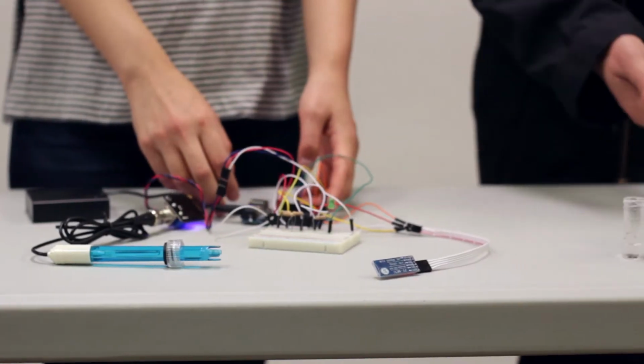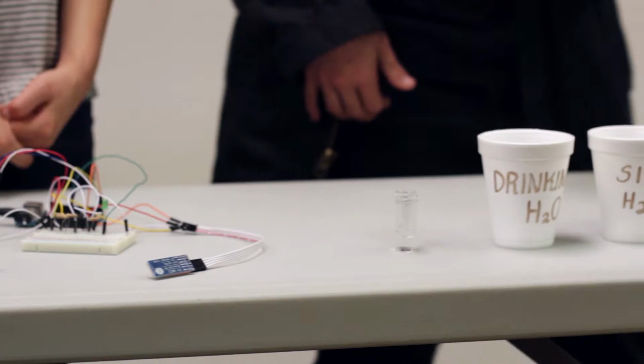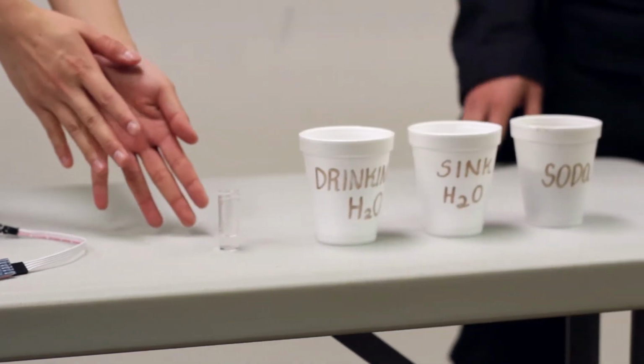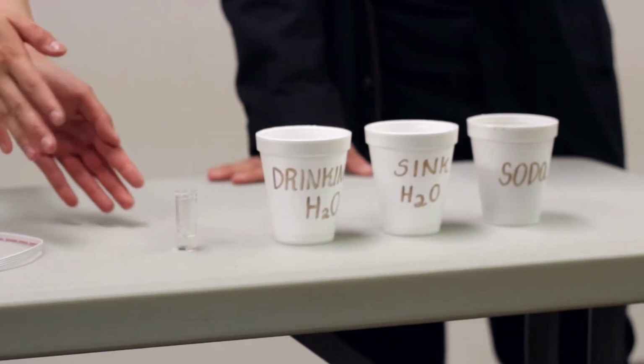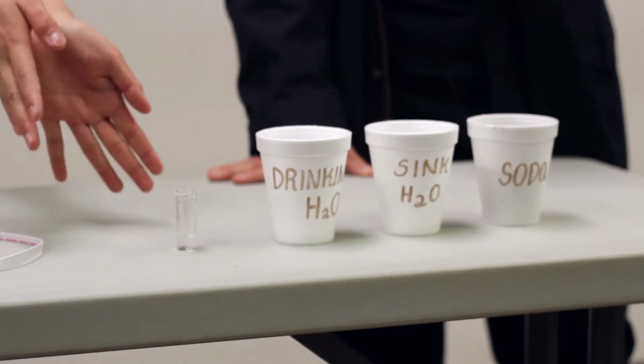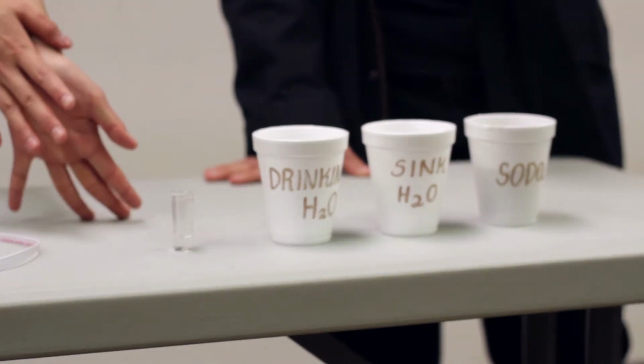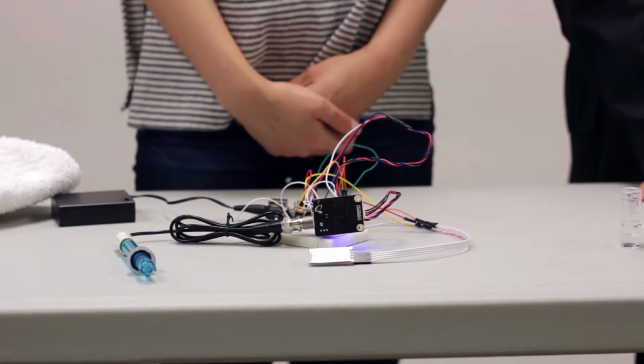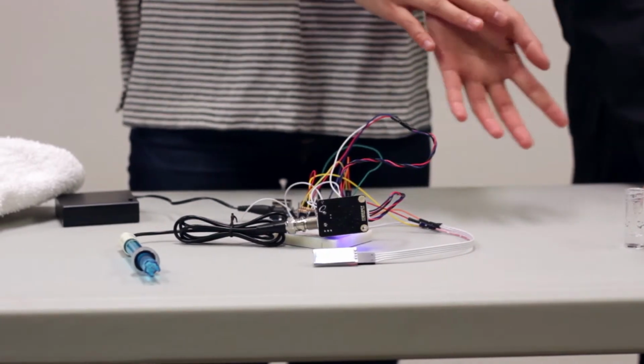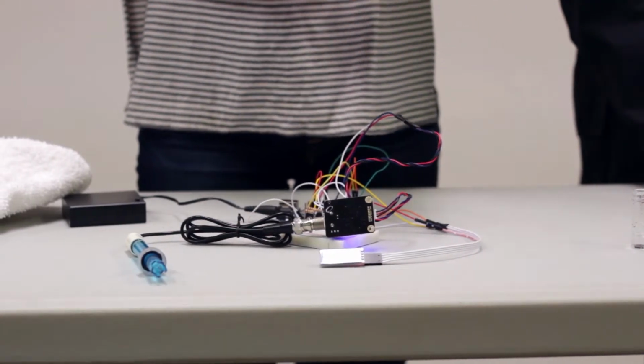Now we can go over examples using these three samples. Here's the pH calibration solution that will level out to the standardized pH level, which is 7. I'm going to test out each solution, and first I'm going to standardize the pH sensor with the calibration solution.